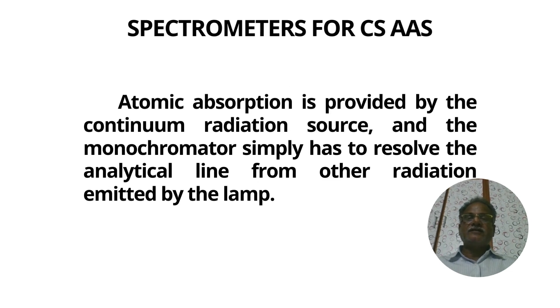Spectrometers for continuum-source AAS use a continuum radiation source, and the monochromator simply has to resolve the analytical line from other radiation emitted by the lamp. For this purpose, a high-resolution monochromator can be used.